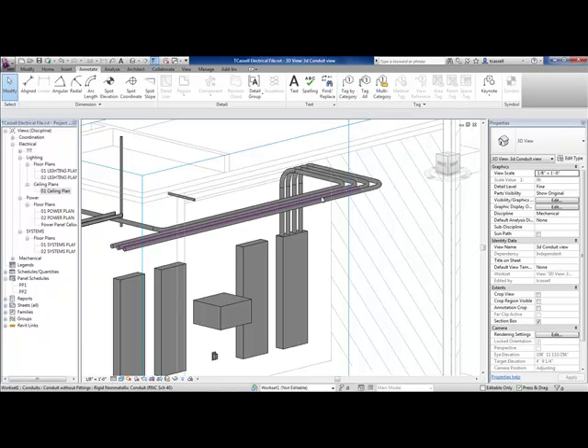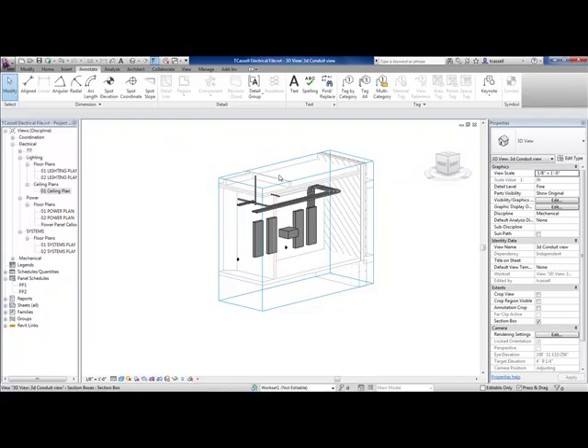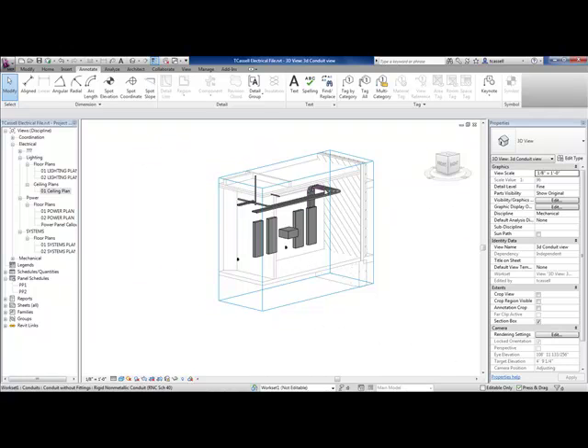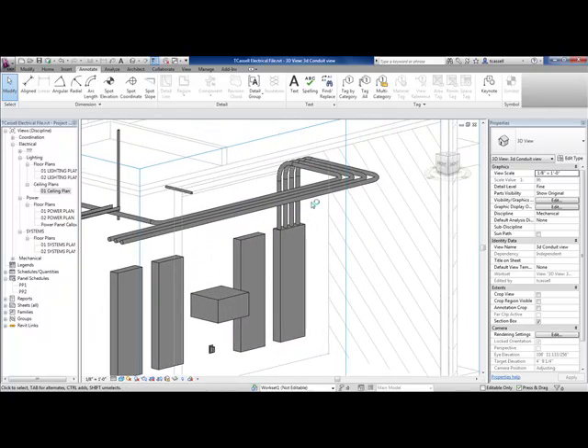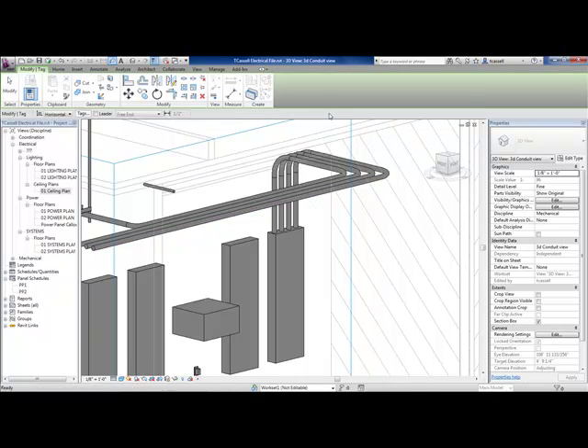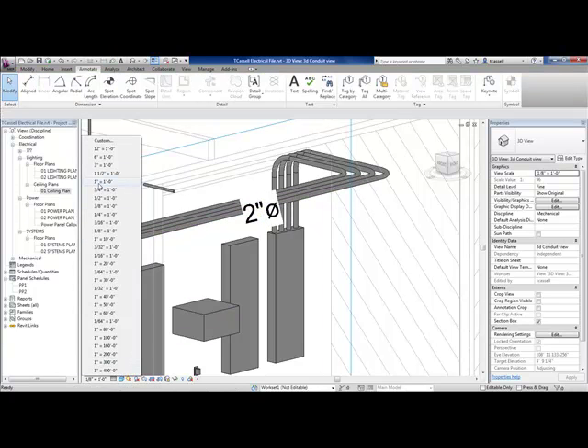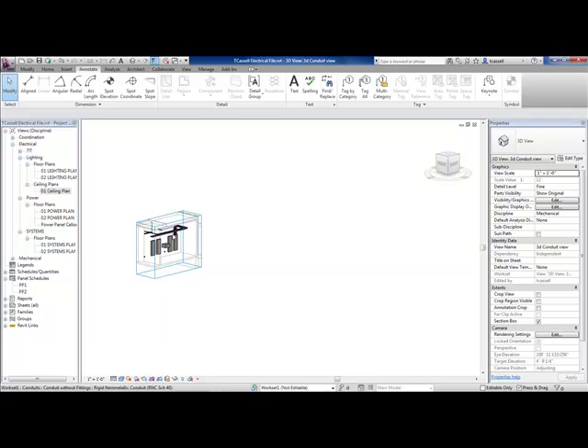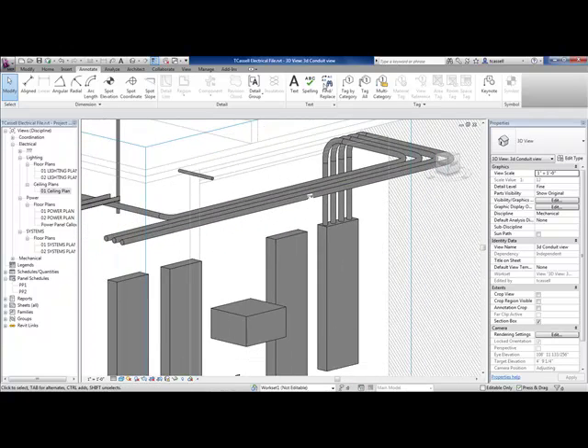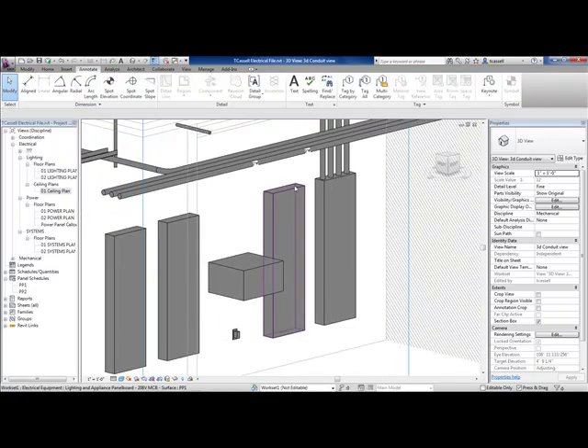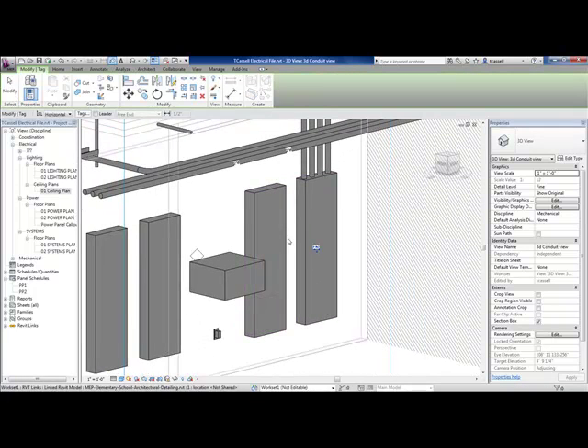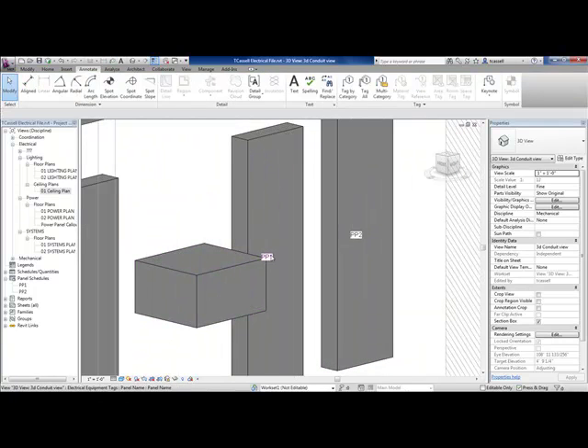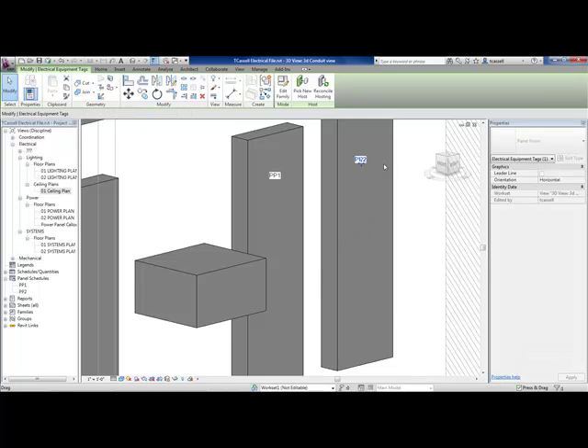This is great if you want to give a very complicated scenario of conduit rising, bending, and turning. I can now give it a 3D look, and I don't have to cheat and use text to tag this conduit. I can do tag by category, click on the conduit, place the tags, and adjust my scale accurately. I can tag each conduit individually, tag conduit in any view. I can tag any object that could be tagged in plan can now be tagged in these 3D views. I can tag with a leader or without a leader, it's completely up to you.